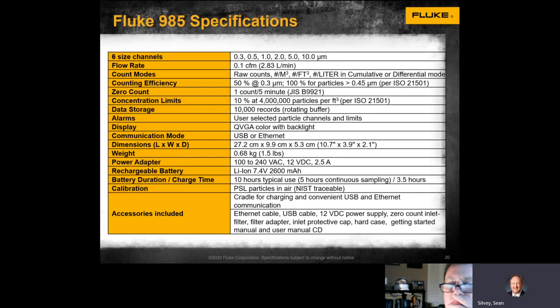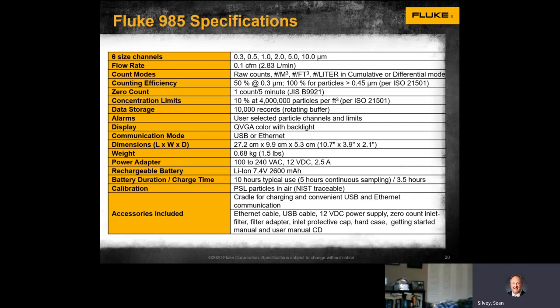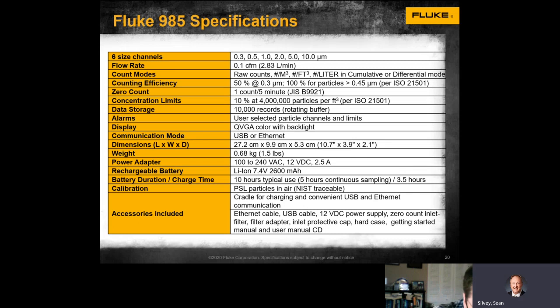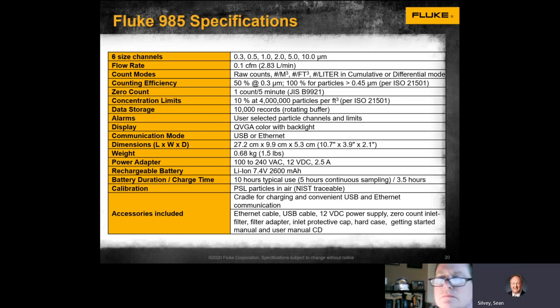Here are the specifications for the 985. The six size channels allow you to see up to six different sizes simultaneously. It has a good flow rate, and you can view counts as cumulative or differential. The unit also features data storage and alarm settings. It is lightweight — you can carry it into different environments, set it up, run it, and get measurements. Battery life is 10 hours typical, and it comes with a base so users can set it up and leave it running in an environment.